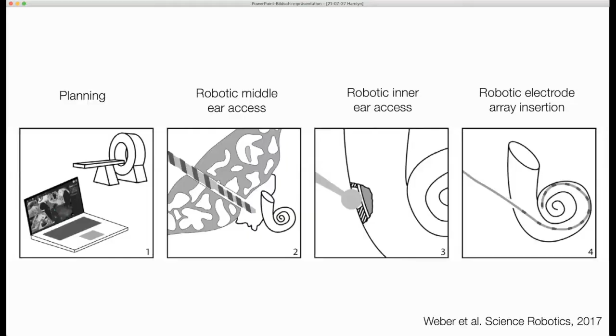In the first step for the middle ear access, again, there is a process model behind. The intention is to drill a 1.8 millimeter tunnel from the skull surface towards the correct point, aiming at the round window in the cochlea. The most critical thing here is that as the system drills through the skull, it needs to pass a section called the facial recess, which is the area between the facial nerve responsible for all the muscles in the face and the taste nerve. The distance between these two nerves on average is only 2.5 millimeters. And you can do simple math, 2.5 minus 1.8 divided by 2. So typically we have 0.4 millimeters of space between the drill hole and the nerve.